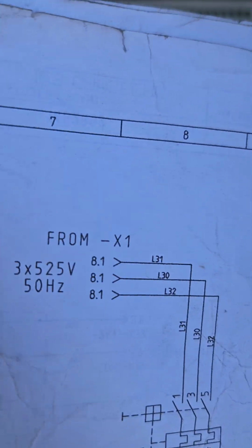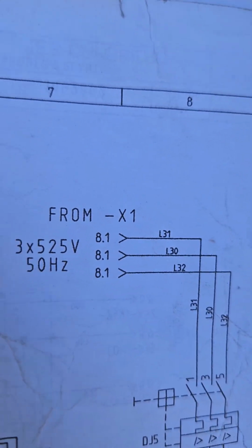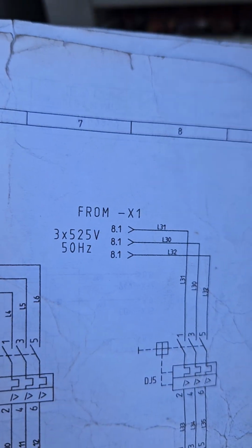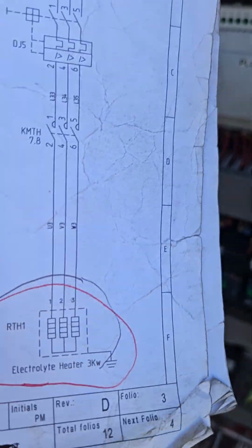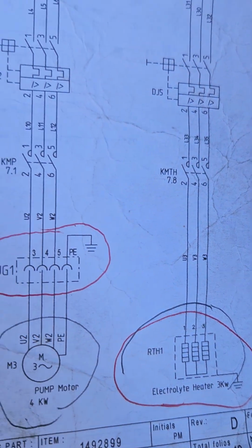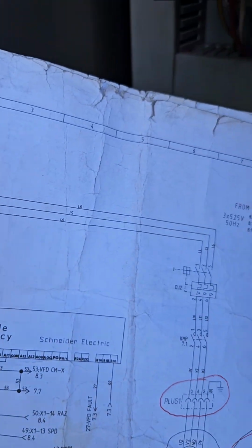The last short thing I'm gonna show you now is this, the other numbers with 8-1. Those numbers are just the page numbers, so it means that the connection you see there is coming from page 8 and is coming column 1. You can see on top we've got columns, column 1s. So that's how you link this page of the drawing to the other pages of the drawing.